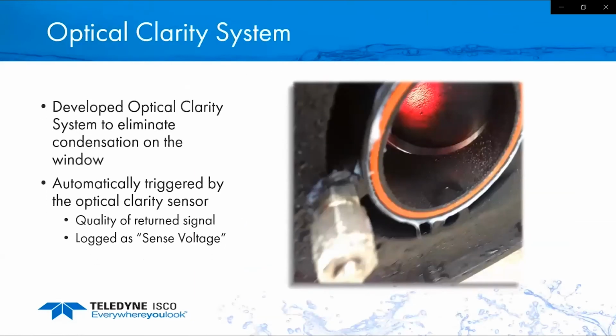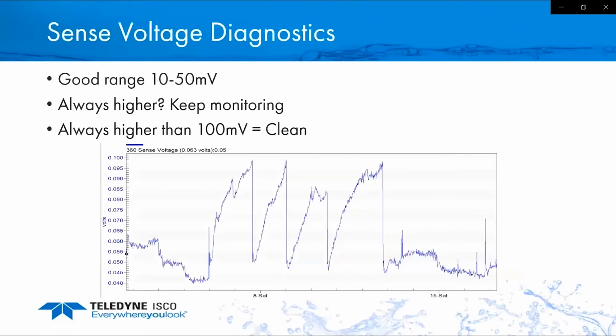And this is an example of the optical clarity system. If it starts getting condensation on there, it will automatically turn on the heater to clean that window off so that you don't have to go out on the site. As I mentioned before, we want to look at the trends, not the instantaneous reading. So condensation starts on the window, the heater kicks on, it drops back down, condensation goes up again, the heater kicks on. So we don't lose any data. It's just automatically warming up that window, cleaning it as needed.